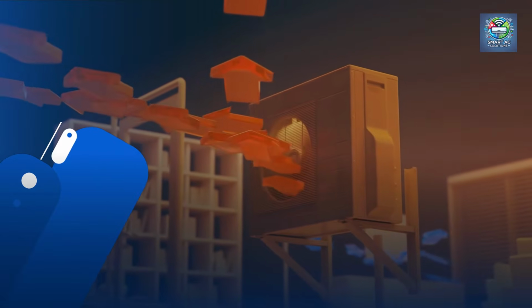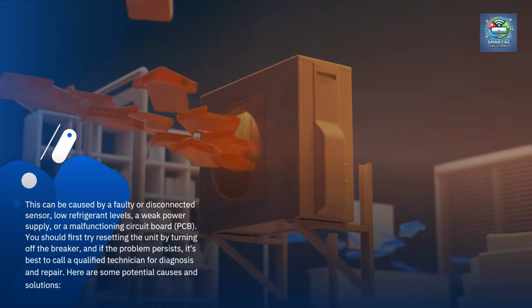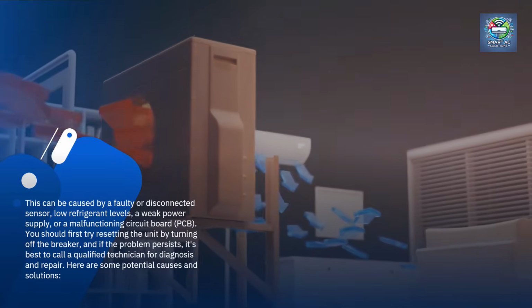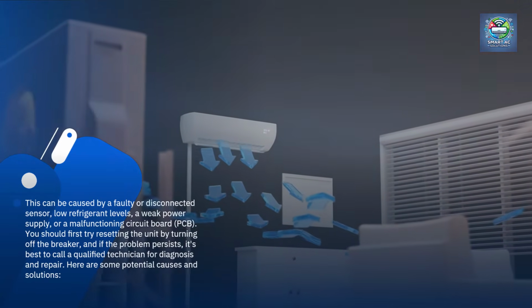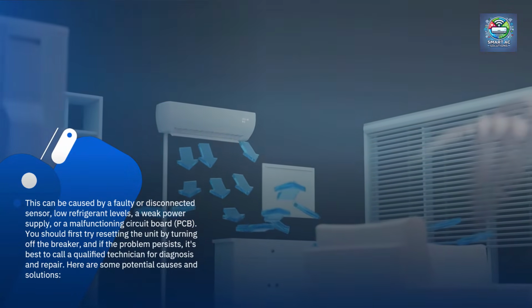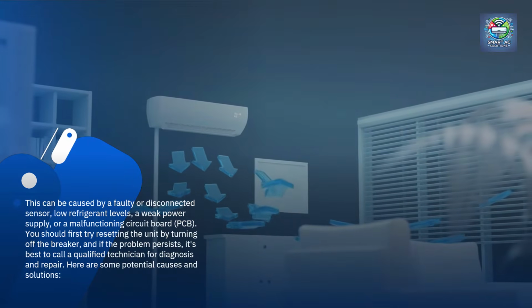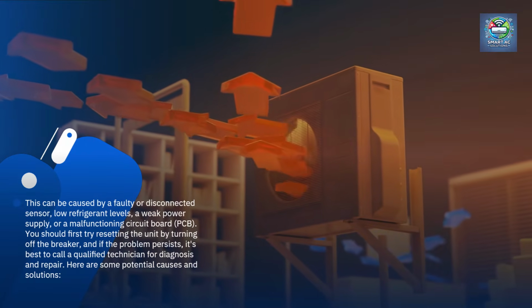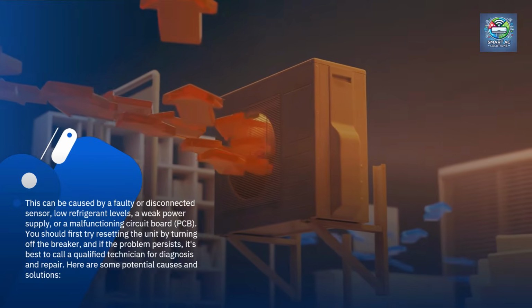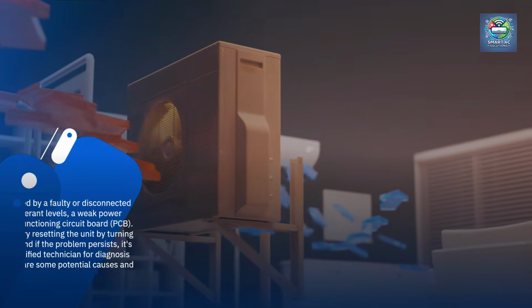This can be caused by a faulty or disconnected sensor, low refrigerant levels, a weak power supply, or a malfunctioning circuit board, PCB. You should first try resetting the unit by turning off the breaker, and if the problem persists, it's best to call a qualified technician for diagnosis and repair.